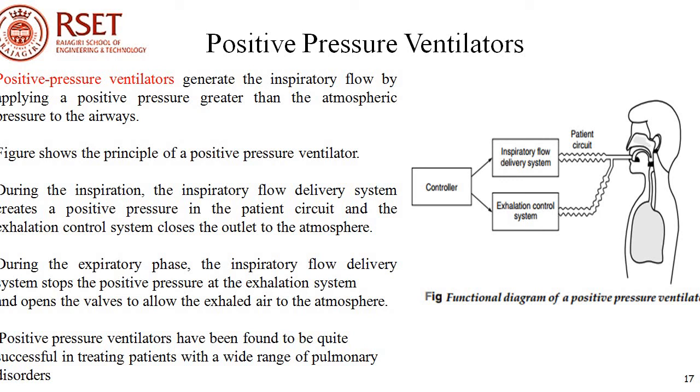Positive pressure ventilators operate either in mandatory or spontaneous mode. In spontaneous breath delivery, the ventilator responds to the patient's effort to breathe independently. Therefore, the patient can control the volume and rate of respiration. Spontaneous breath delivery is used for those patients who are on their way to full recovery but are not completely ready to breathe from the atmosphere without mechanical assistance.